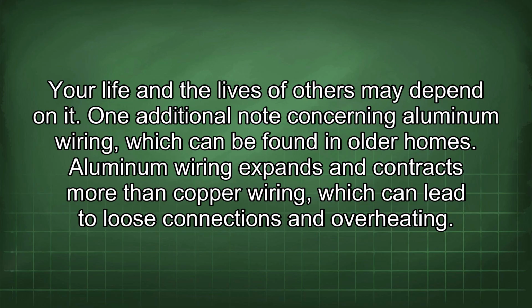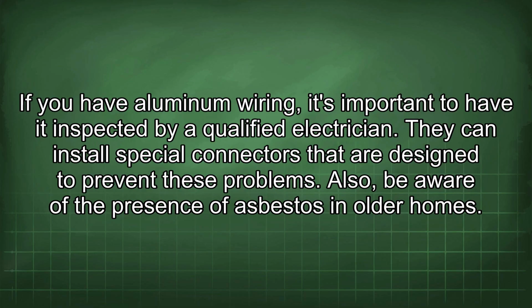One additional note concerning aluminum wiring, which can be found in older homes. Aluminum wiring expands and contracts more than copper wiring, which can lead to loose connections and overheating. If you have aluminum wiring, it's important to have it inspected by a qualified electrician. They can install special connectors that are designed to prevent these problems.